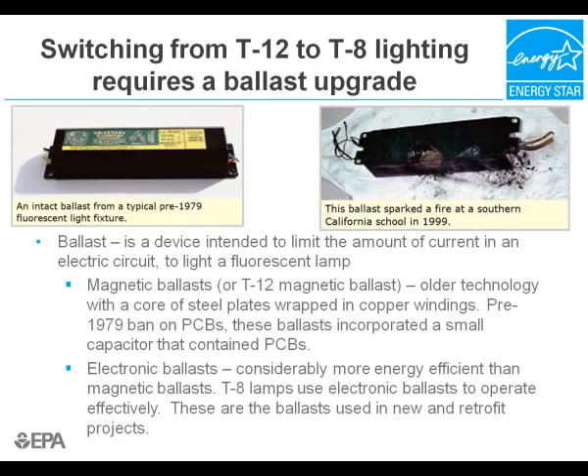Switching from T12 to T8 lights requires a ballast upgrade, and a ballast is a device intended to limit the amount of current into the electric circuit to light up a fluorescent lamp. The T12 magnetic ballasts are older technology with a core of steel plates wrapped in copper windings. Before the 1979 ban on PCBs, these ballasts incorporated a small capacitor that contained PCBs. Some of these ballasts may leak PCBs and continue to operate and may be prone to overheating and sparking a fire. An electronic ballast is considered more energy efficient than a magnetic ballast.